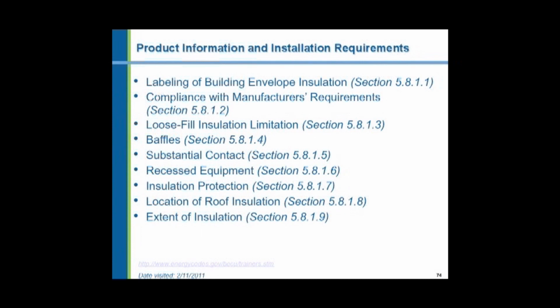Labeling of the building envelope insulation, and labeling is easily done if the insulation has a facing on it, whether an aluminum foil facing or a kraft paper, because it's easy to print the data on the insulation facing right there, the R value, and any other data. However, if you have a loose fill insulation, blown in insulation, sprayed on urethane or isocyanurate or any of the other insulations, sprayed on chopped cellulose insulation, then you have to rely on manufacturer's data, certification from the manufacturer and the applicator that the insulation installed in this manner, in this thickness, will guarantee this R value. And so those things must be submitted as part of the package.